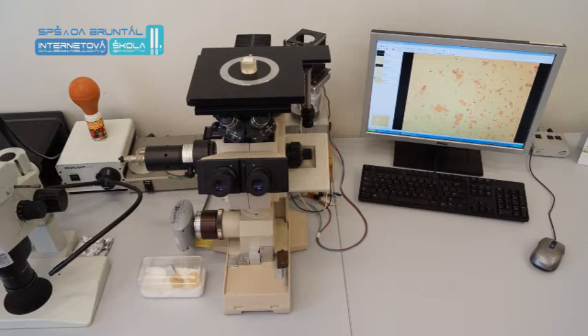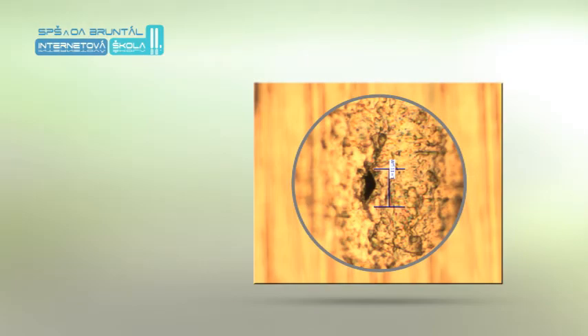The metallographic microscope used here is well equipped for observation in bright and dark field. In bright field observation, part of the light emitted by the source is reflected from plan-parallel glass, passes through the objective and falls perpendicular to the mount surface. Depressions, grooves and irregularities that do not reflect rays into the objective are dark.